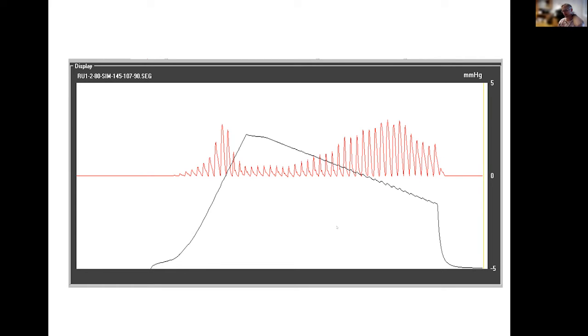And by the way, this is mainly also the difference between the devices which measure blood pressure on the way up, when they just pump the pressure up. They're using these pressure pulses, and in classical devices you measure blood pressure when deflating. This means that they're using this side of pressure pulses. And the mathematical algorithms in these devices just put some envelope on these pressure pulses and then calculate the systolic and diastolic pressure from it. Why am I showing you this? Because what we did when testing simulators, we were interested in repeatability of such pulses.